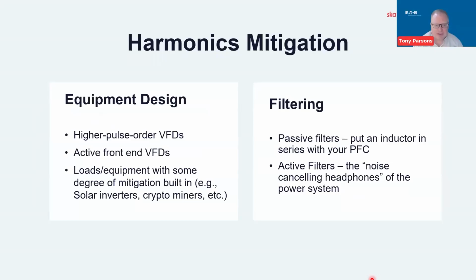Yeah, there's several things, Steve. One would be equipment design, right? We talked about VFDs a little bit already, or adjustable speed drives, if you prefer. One of the most significant sources of harmonic distortion in the system, you can use higher pulse order VFDs instead of a 6 pulse drive, a 12 pulse or 18 pulse. And not going into the technical details, but those are designed to help mitigate and greatly reduce some of the highest harmonic currents that may otherwise be injected back into the systems.